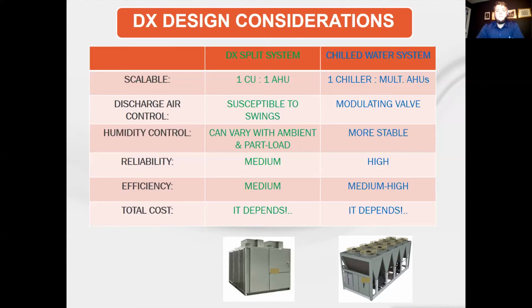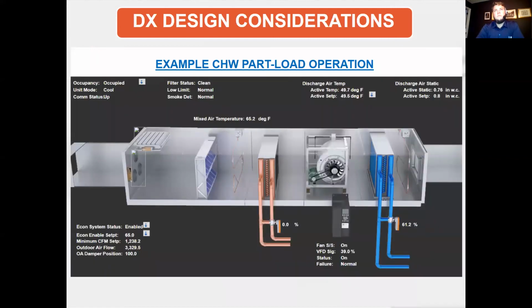And in the next slide, I'd like to show you one of the benefits that we see to a chilled water system. This is actually the air handler in our office. I had somebody take a screenshot yesterday of what it was doing about noon yesterday. If you remember, it was kind of a chilly day. It shows the air temperature was 65 degrees and the unit was in economizer. Now this is a 16,000 CFM air handler that serves an 18,000 square foot office.